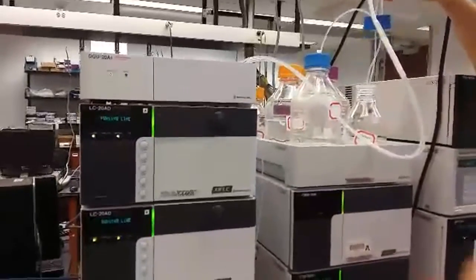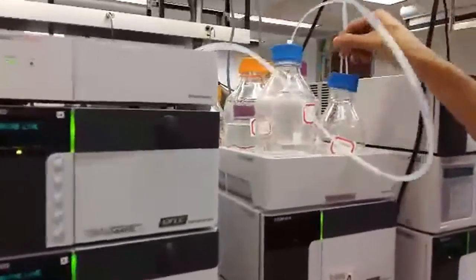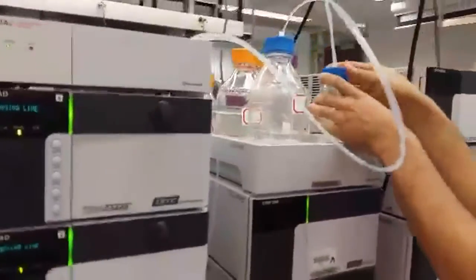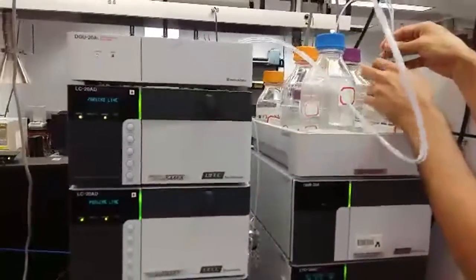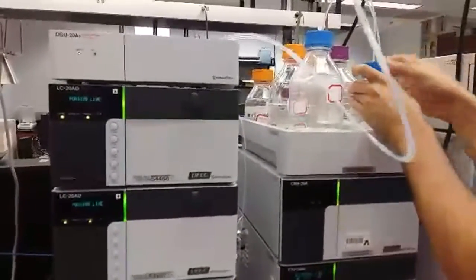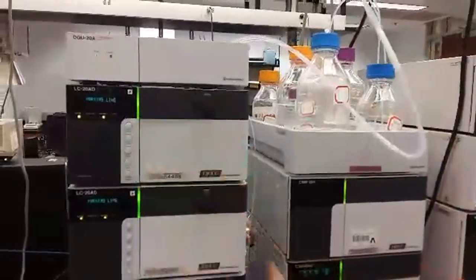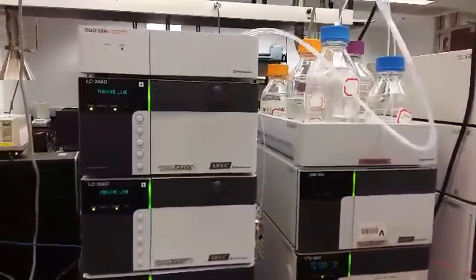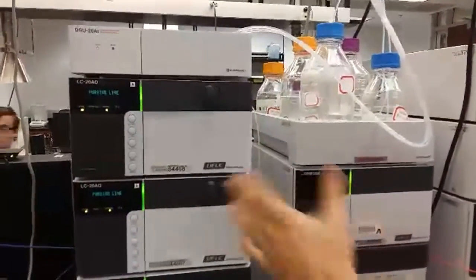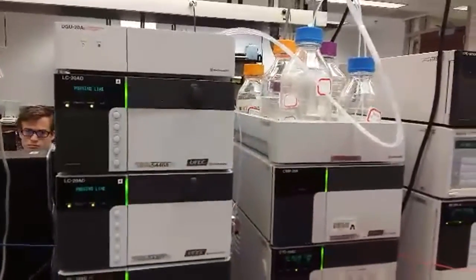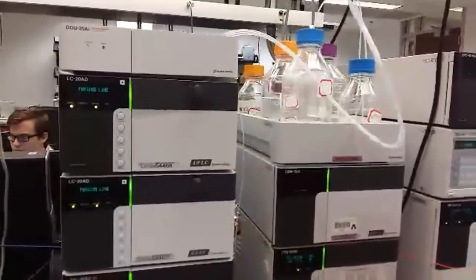You can see the bubbles. Now we are fine. We will put it back in the reservoir and wait for the pump to be steady. It's going to take almost 3 to 5 minutes for the pump to do the purging process, and then you have to close these knobs and wait for the pressure to increase.